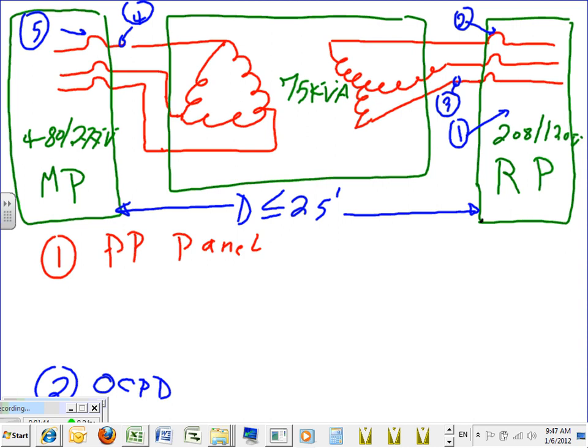The transformer has already been sized at 75 kVA. I need to size the panel that goes with it, the conductor that feeds the transformer, the overcurrent protection device on the primary, the overcurrent protection device on the secondary, and the cables between the transformer and the panel. This involves the transformer tap rule - 'D' stands for distance equal to or less than 25 feet.